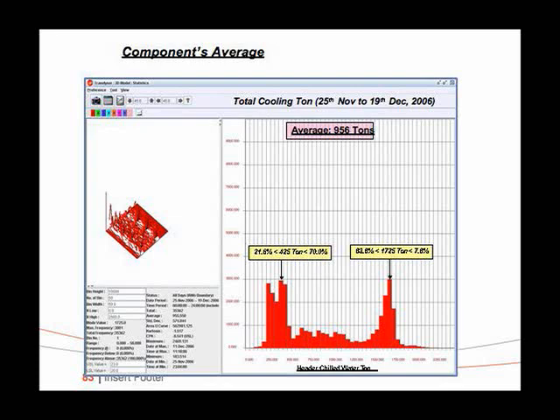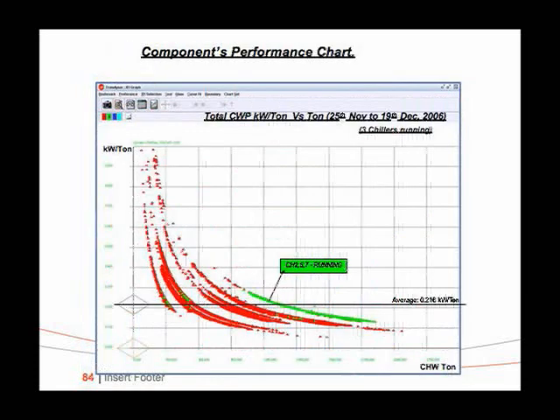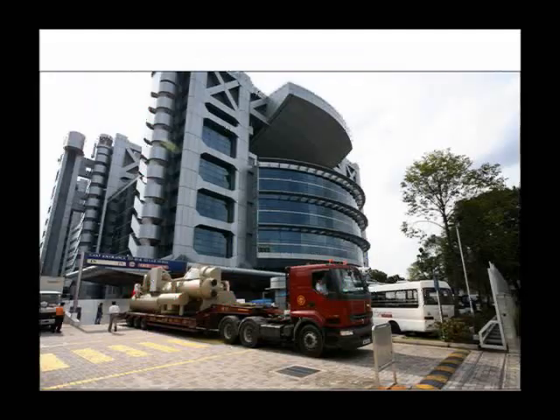All the component averages, in this case, cooling tons, etc. Kilowatt per ton for condenser water pumps. Of course, there's a lot more, but running out of time. TRANE. Now, all spell after me, T-R. We supplied machines at 0.49. We guaranteed 0.603 for the system for an initial period of 2 years with optional renewal for 8 years. So we are prepared to go 10 years at 0.6. And this is not new because the Hyatt Hotel in Singapore is now 8 years old.